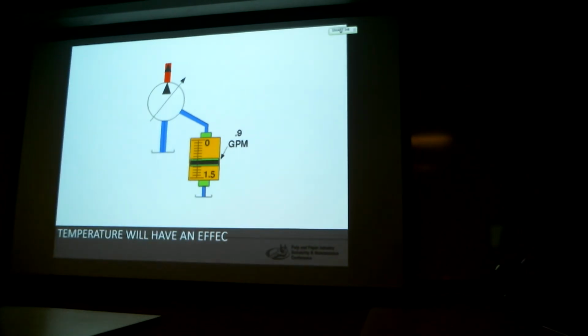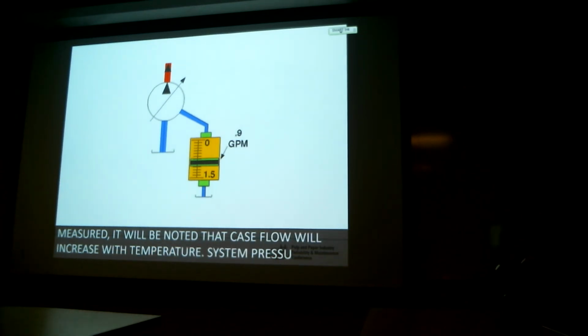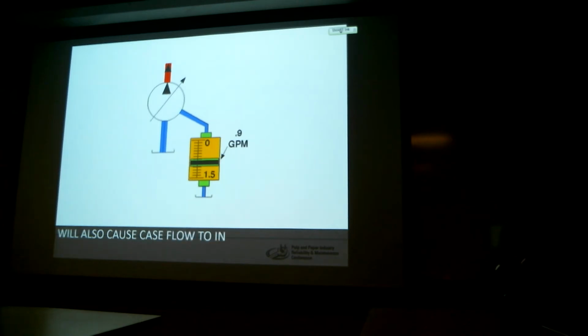The higher the fluid temperature, the lower its viscosity will be, and the more case flow will pass. The first year that the case drain is measured, it will be noted that case flow will increase with temperature. System pressure will also cause case flow to increase by an amount proportional to the pressure. So it would be wise to monitor each case drain monthly and record the minimum and the maximum flow through a complete machine cycle, thus giving us a benchmark of what is normal for August as well as what's normal for February and every other month. Most pump manufacturers include normal ranges for case flow in their documentation.